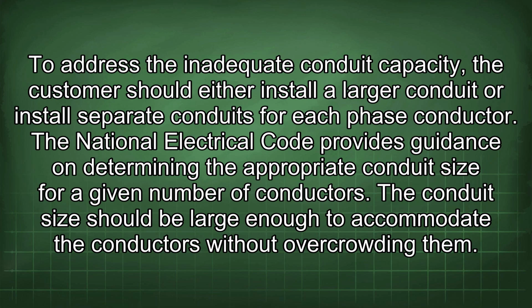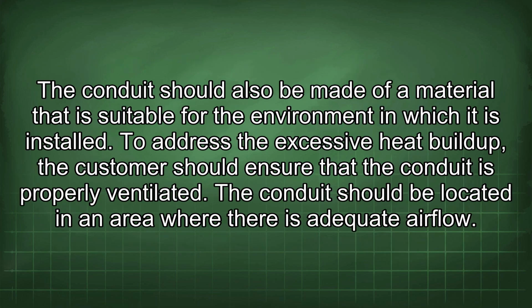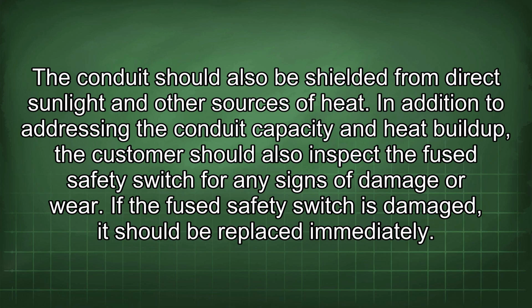The National Electrical Code provides guidance on determining the appropriate conduit size for a given number of conductors. The conduit size should be large enough to accommodate the conductors without overcrowding them. The conduit should also be made of a material that is suitable for the environment in which it is installed. To address the excessive heat buildup, the customer should ensure that the conduit is properly ventilated. The conduit should be located in an area where there is adequate airflow. The conduit should also be shielded from direct sunlight and other sources of heat.